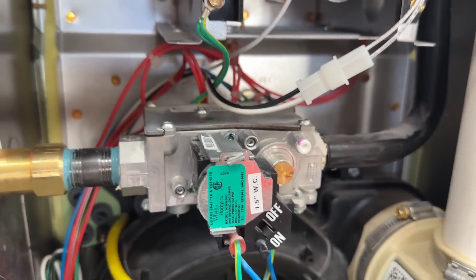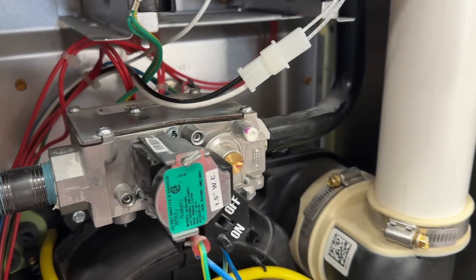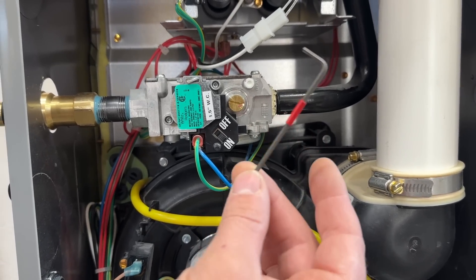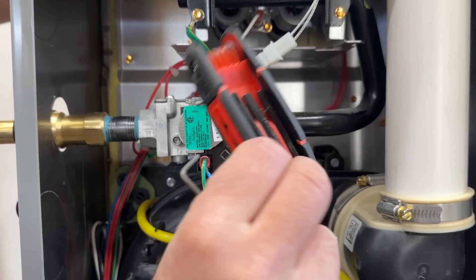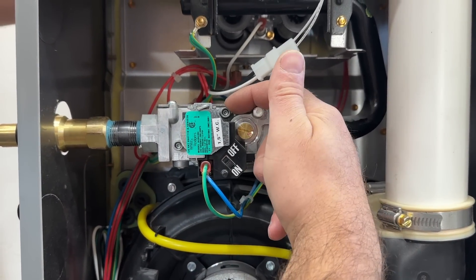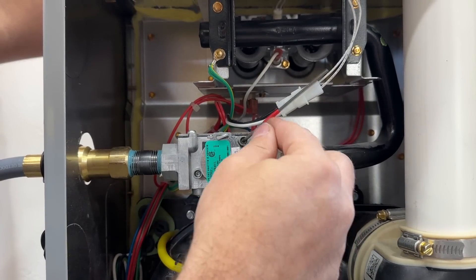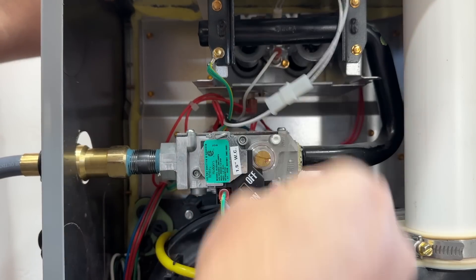To start, make sure the furnace is off — you can either switch it off or unplug it so nothing comes on when we hook our manometer up. Even if you leave the port open for a couple of seconds just to attach it, it's not going to do any damage. The Fieldpiece kit comes with this Allen wrench — it's 3/32 — and we're simply going to put it in. You do not need to take this plug out; just go maybe a half turn, that's all that's needed.